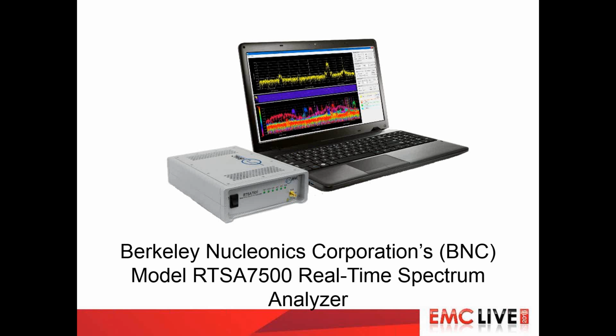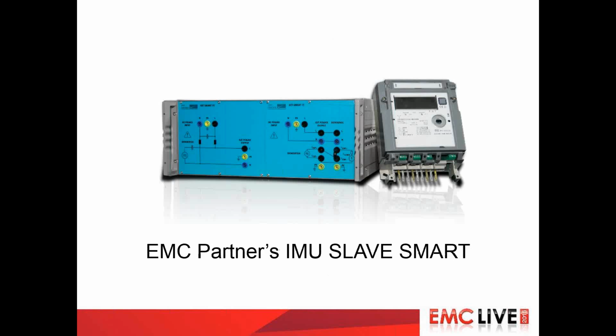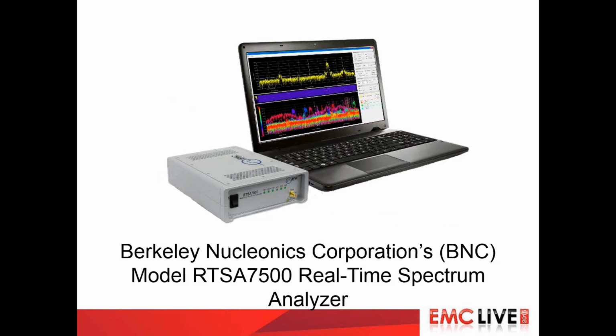Go ahead. Pat, once you've used real-time spectral analysis, you really don't want to go back. And I noticed this one's real-time bandwidth is 100 megahertz. The value in that is if a transient does come through, it will capture it and display that result. It's different than a swept measurement where you're going from a low frequency to a higher frequency, and you're hoping that you're at the right frequency to capture the transient. This is extremely valuable for that type of measurement. I've looked at other spectrum analyzers with real-time analysis, and you can actually see multiple Wi-Fi access points on the same channel, which is amazing. A swept analyzer would never be able to do that.